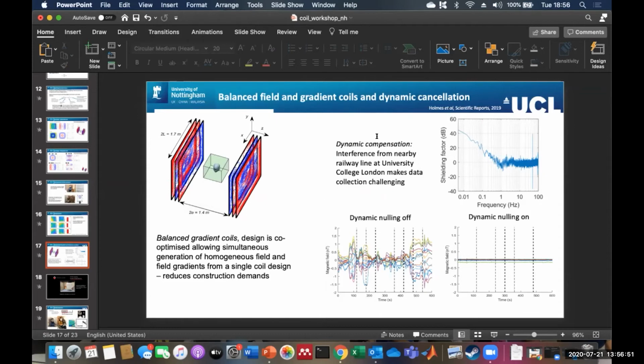We also looked at dynamic compensation. This is data taken in London, where we put some coils into an MEG system at UCL that was very close to the London Underground train line. The London Underground is quite regular. You have trains every 2 or 3 minutes, so you can't even get through a 10-minute scan without having about 10 trains running. You can see the artifacts that they're generating are quite large, and obviously that would mask the brain activity that we're trying to find.